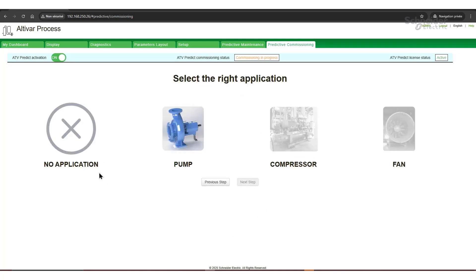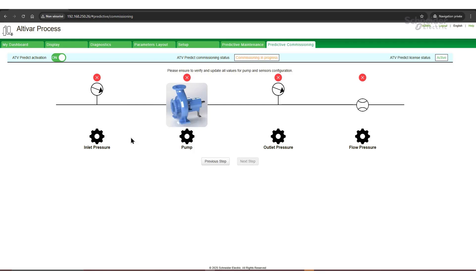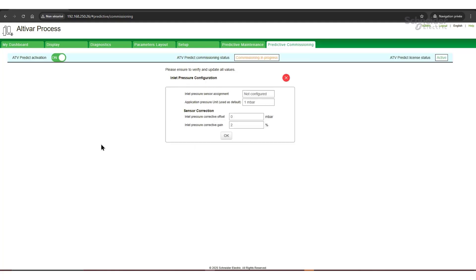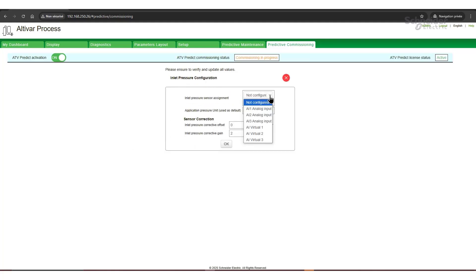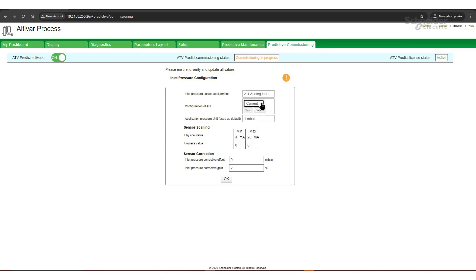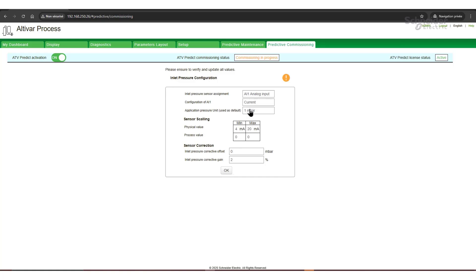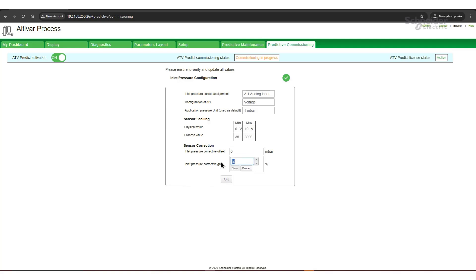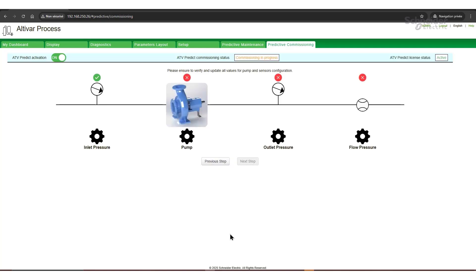Next step, select the right application. We select the pump and view the system, showing inlet pressure, the pump, outlet pressure, and flow meter. The status is displayed above each device. We select inlet pressure. Our pressure sensor is connected to AI1 with a voltage signal. Use millibar for units. Now we need to scale the sensor to align the physical and process values. We adjust the corrective offset and gain if needed. We can see the status is changed to green.